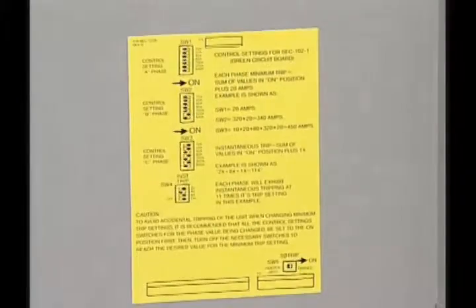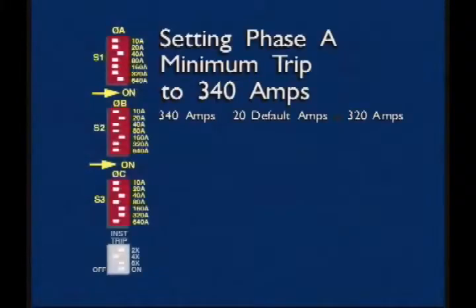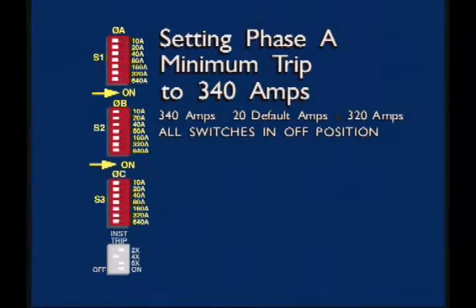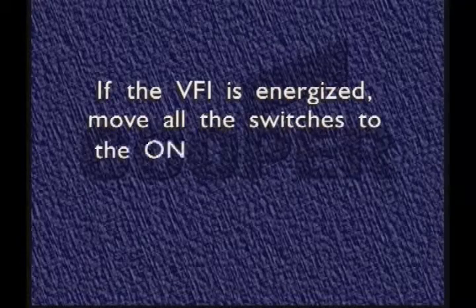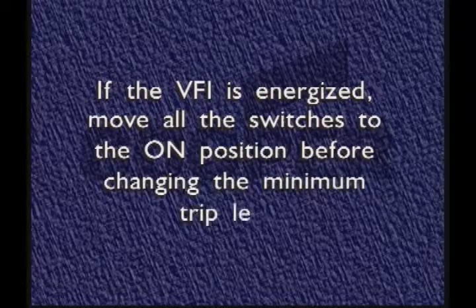10 amp increments. On a de-energized unit, for example, let's say the desired minimum trip value for phase A is 340 amps. Refer to the control settings decal. 340 amps minus the 20 amp default minimum trip setting leaves 320 amps to be programmed. Make sure that all the switches on the bank are turned off. Identify the switch numbered 320 and turn it on. If the VFI is energized, move all the switches to the on position before changing the minimum trip level. This will prevent an inadvertent trip operation.